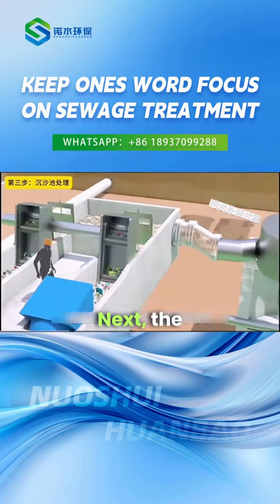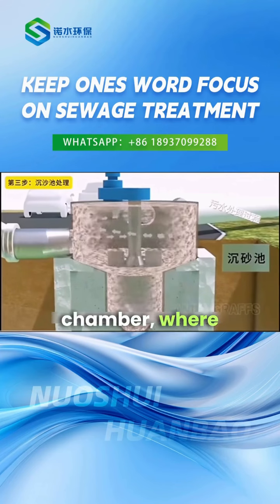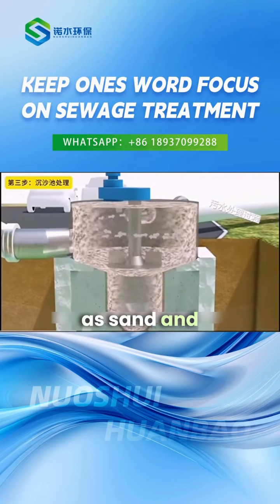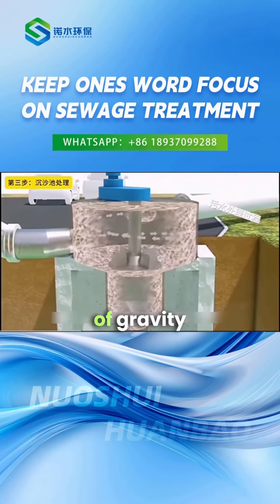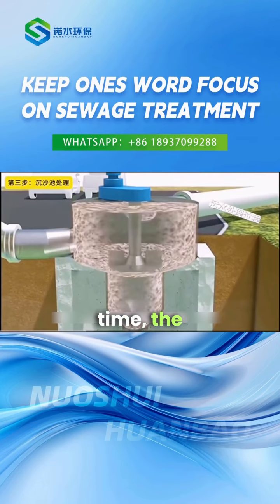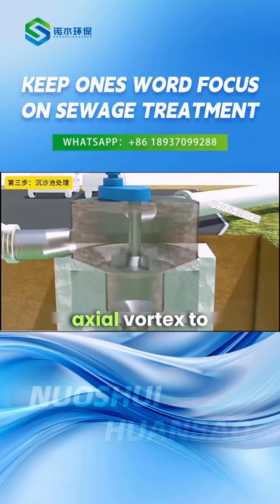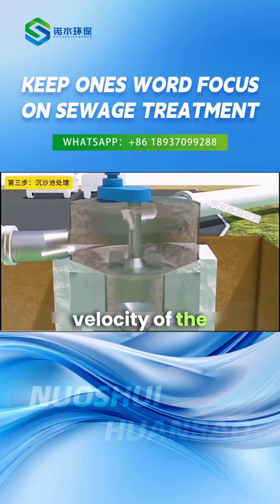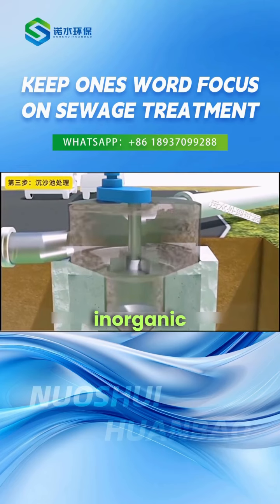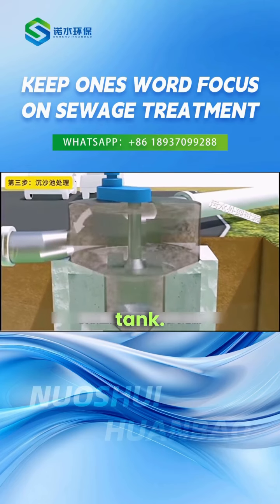equipment. Next, the wastewater enters the grit chamber, where larger inorganic particles such as sand and coal cinders are removed by the principle of gravity settling. At the same time, the rotating impeller in the tank creates an axial vortex to reduce the flow velocity of the wastewater, allowing the heavier inorganic particles to settle to the bottom of the tank.